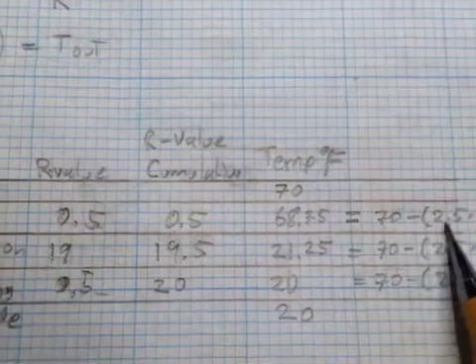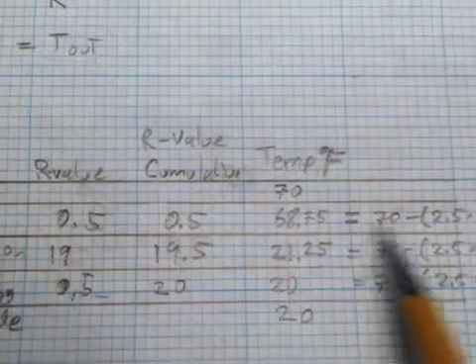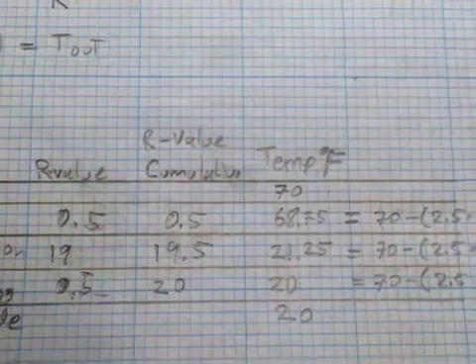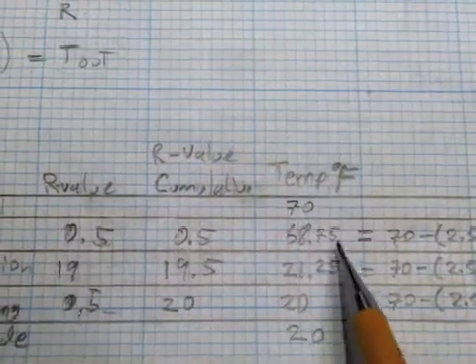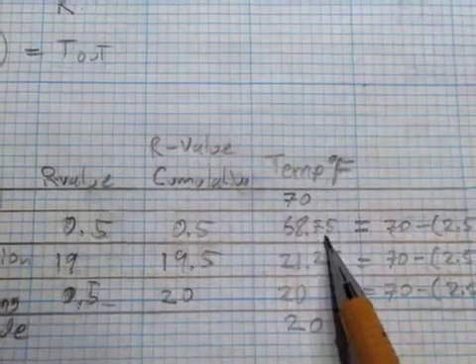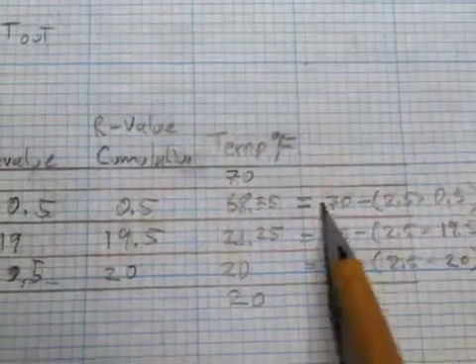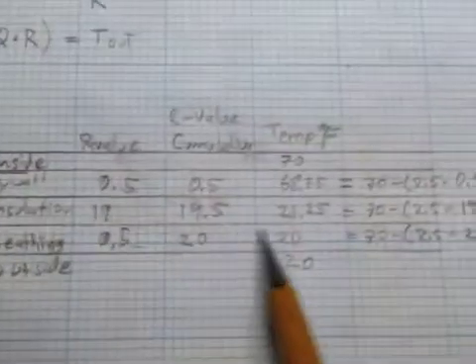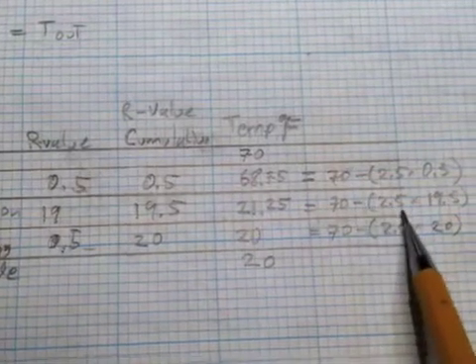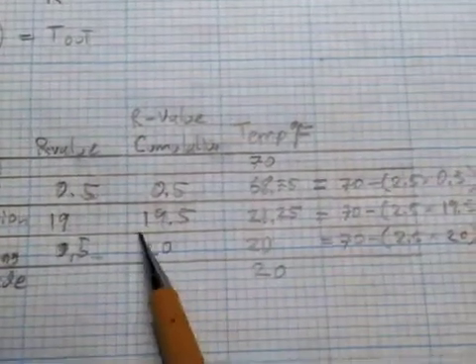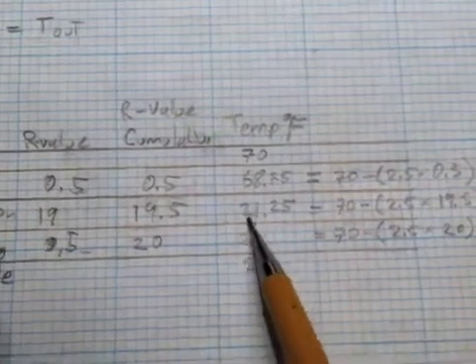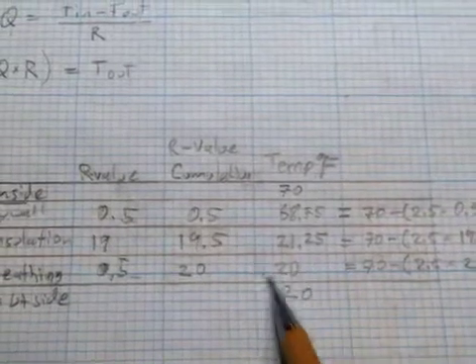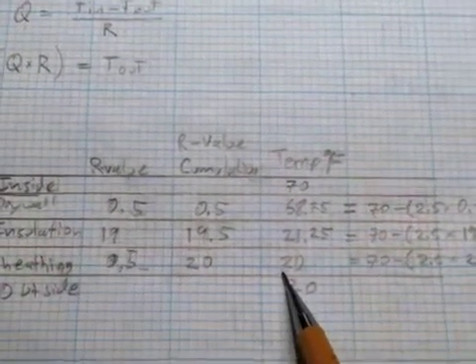For the drywall: 70 − (2.5 × 0.5) = 68.75°F on the outside of the drywall, which is also the inside face of the insulation. For the insulation: 70 − (2.5 × 19.5) = 21.25°F on the outside of the insulation, which is the inside face of the sheathing. For the sheathing: 70 − (2.5 × 20) = 20°F — not surprisingly, this matches our outside temperature exactly.